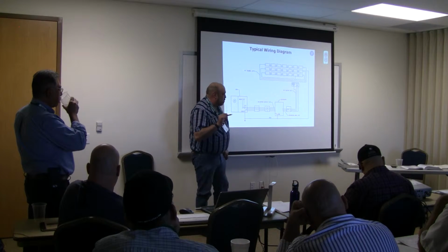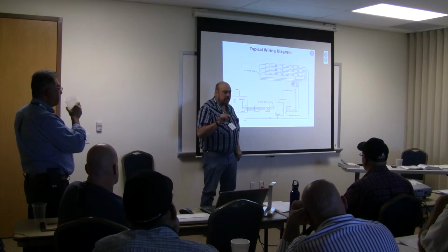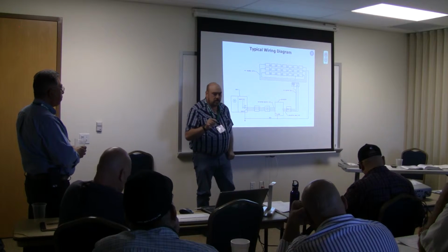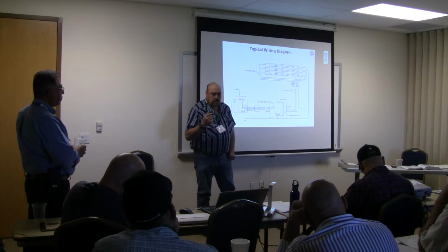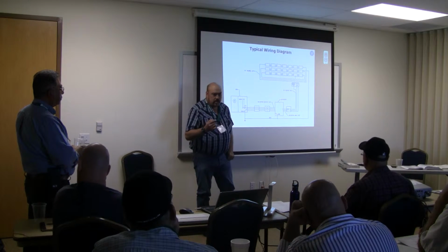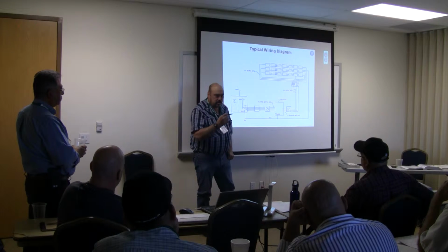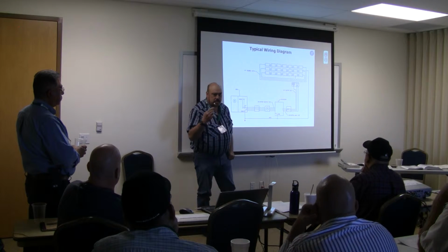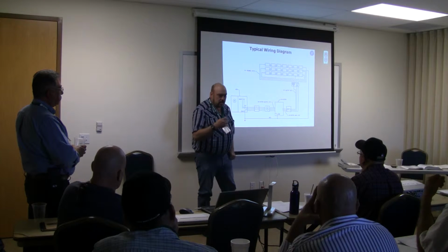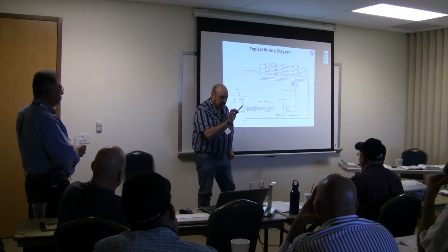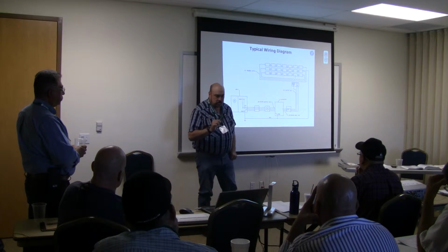Now, there is a more accurate way, and sometimes designers will do it that way. You're going to be using temperature coefficients. And on the cut sheet, you're still going to use the lowest ambient temperature of the area that you're in, but you're going to use the information from the standard test conditions off those temperature coefficients.